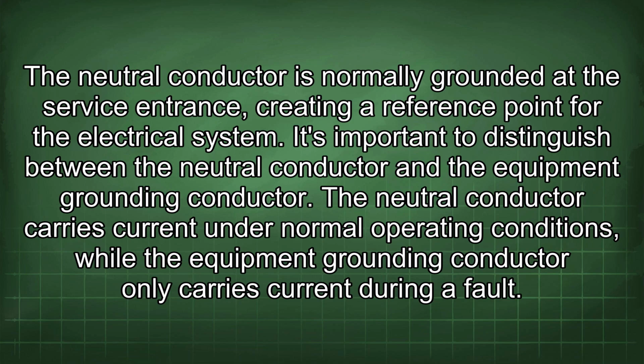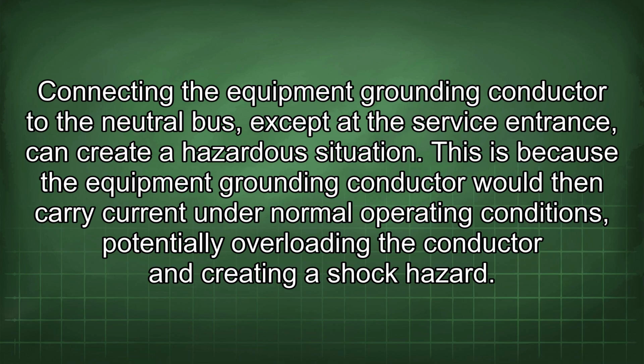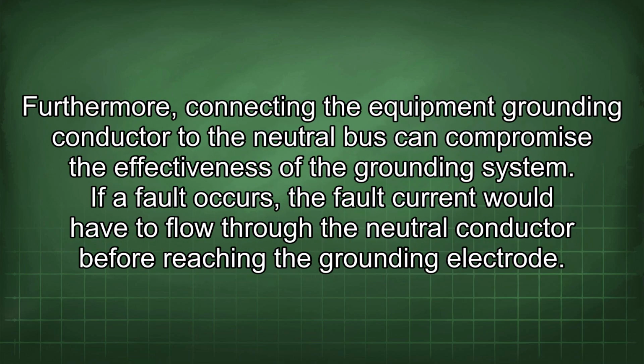It's important to distinguish between the neutral conductor and the equipment grounding conductor. The neutral conductor carries current under normal operating conditions, while the equipment grounding conductor only carries current during a fault. Connecting the equipment grounding conductor to the neutral bus, except at the service entrance, can create a hazardous situation. This is because the equipment grounding conductor would then carry current under normal operating conditions, potentially overloading the conductor and creating a shock hazard. Furthermore, connecting the equipment grounding conductor to the neutral bus can compromise the effectiveness of the grounding system. If a fault occurs, the fault current would have to flow through the neutral conductor before reaching the grounding electrode.